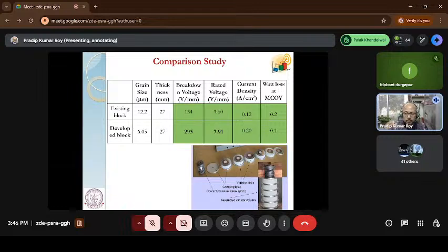So earlier, if you remember, to make a 400 kV surge arrestor I was using 133 blocks. Now my rating is 7.9, almost 8. So if I make a 400 kV arrester, I need only 50 blocks. Today people are talking about 1400 kV surge arrestors, and if I make them with a rating of around 8, you can imagine that I can reduce the total surge arrestor height.